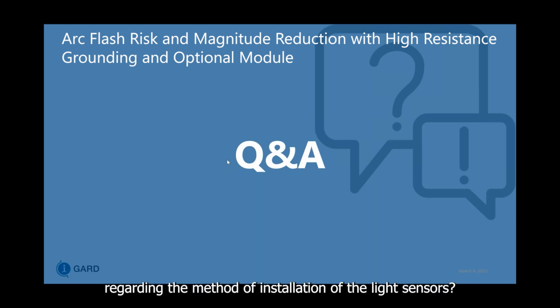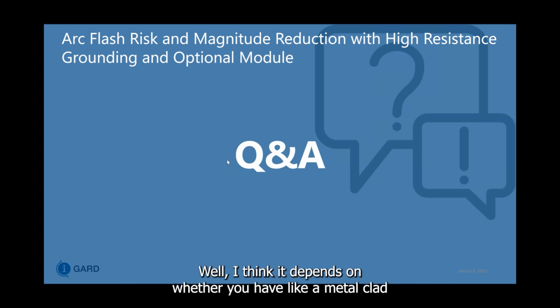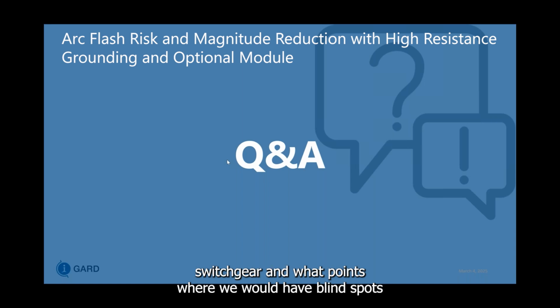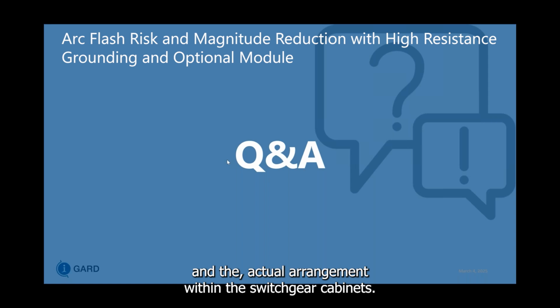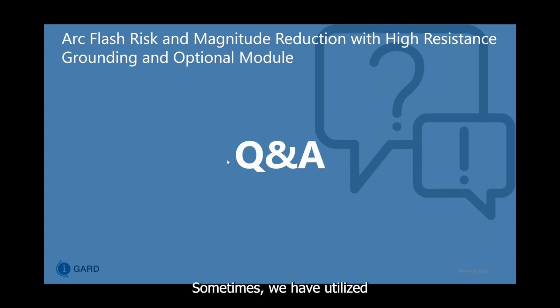Is there a protocol regarding the method of installation of the light sensors? Well, I think it depends on whether you have metal clad switchgear and what points would have blind spots in the actual arrangement within the switchgear cabinet. Sometimes we have utilized probably 3 sensors per section, so that might be an initial starting point for this design.